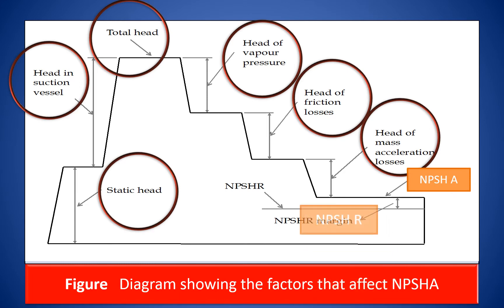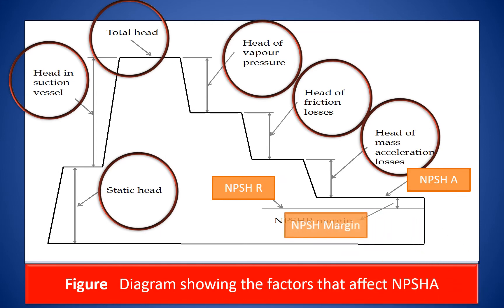As the liquid passes from the pump suction to the eye of the impeller, velocity increases and pressure decreases. There are also pressure losses due to shock and turbulence. As the liquid strikes the impeller, the centrifugal force of the impeller vanes further increases the velocity and decreases the pressure. Broadly, there are two kinds of losses: one, friction losses; and two, losses due to acceleration. The NPSH required is the positive head in meters of liquid available at the pump suction to overcome these pressure losses and keep the liquid above vapor pressure.